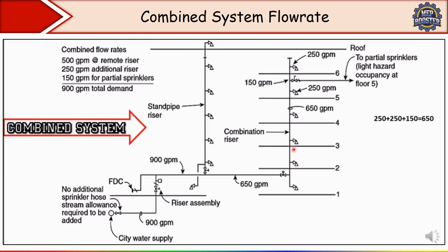So here we have 150 GPM, see how to calculate the combined flow rate. It is very simple. 150 GPM for partial sprinkler we have considered as per NFPA. Then 500 GPM, because you know that when you calculate here, for the most remote standpipe 500 GPM flow, and for additional 250. So when you add, you will get 900 GPM total demand. Okay, simply in this way we need to calculate.